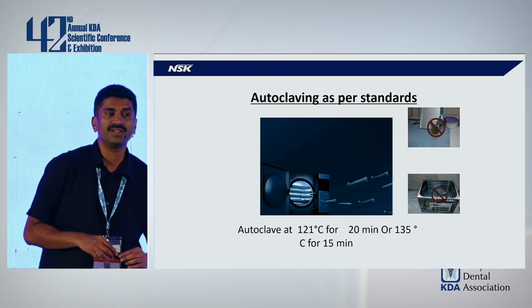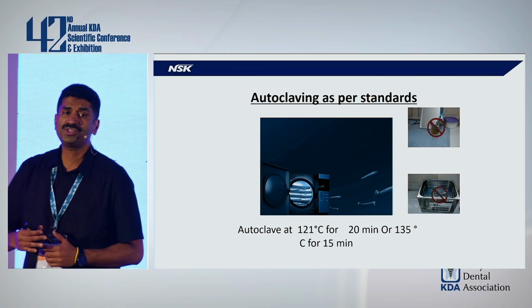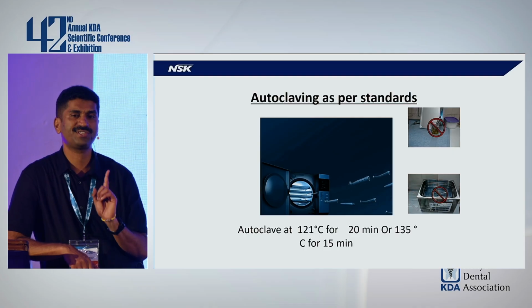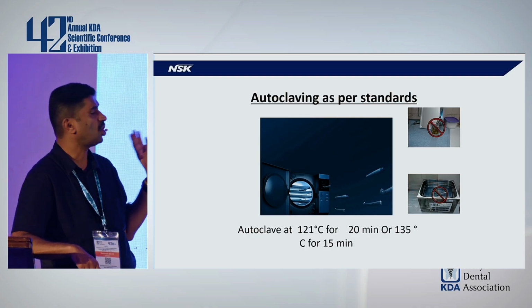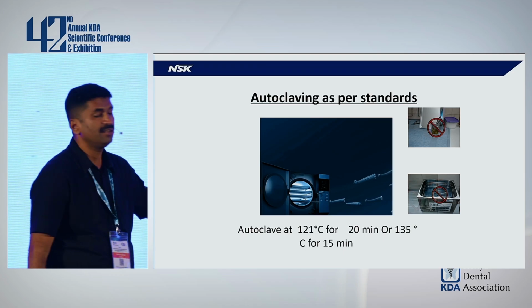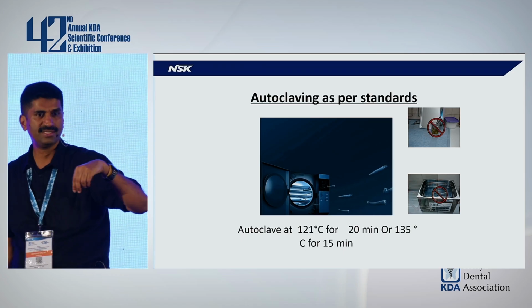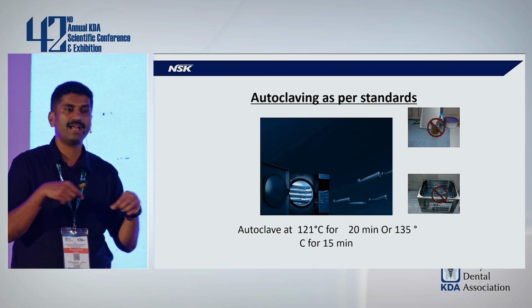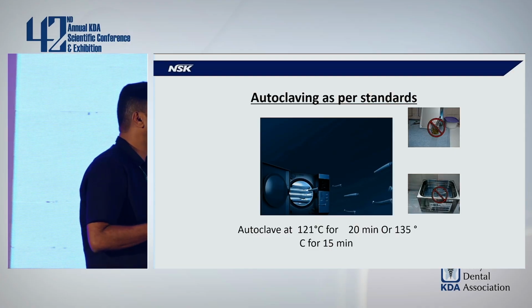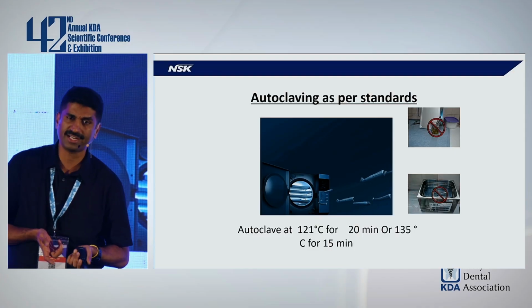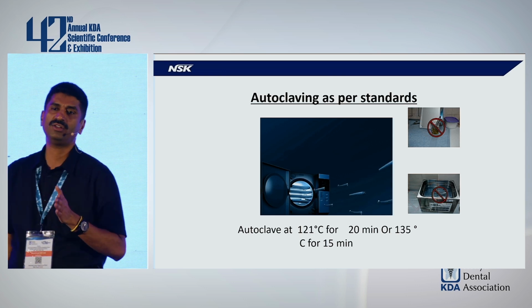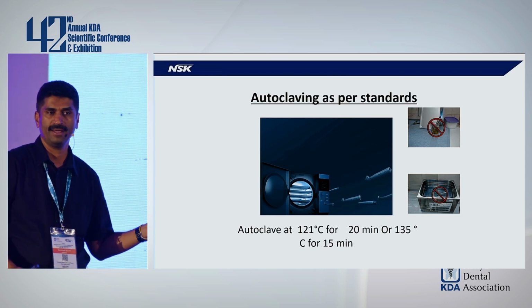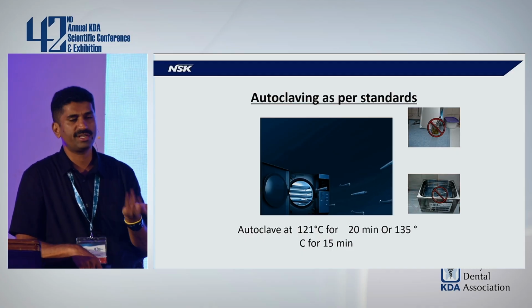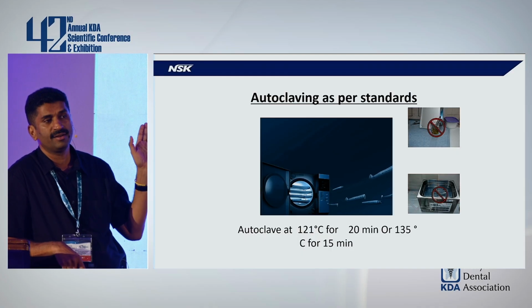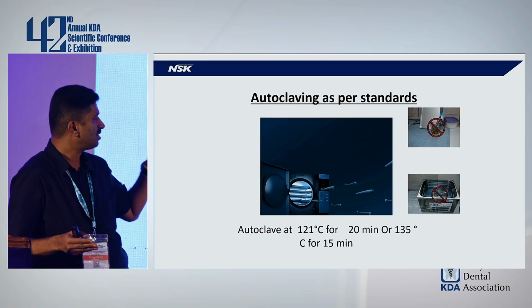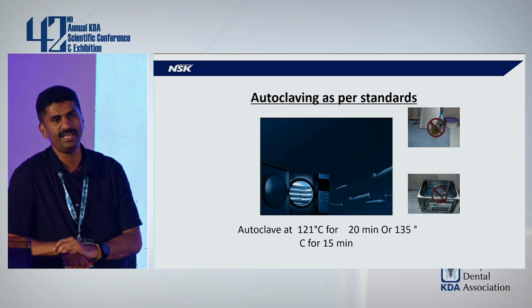Then comes sterilization. When it comes to sterilization, there is only one method of sterilization for dental handpieces, which is autoclaving. We do not recommend dipping your handpieces into any chemical solutions. We do not recommend putting your handpieces into an ultrasonic bath. We do not recommend putting your handpieces into glass bead sterilizers. The one and only methodology of sterilization is autoclaving. So you can use B class, S class, whatever type of autoclave you have, and put the handpiece in a sterilization pouch and put it in the autoclave. That will take care of the sterilization.